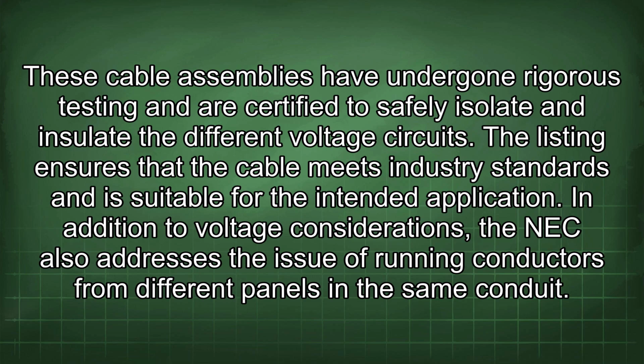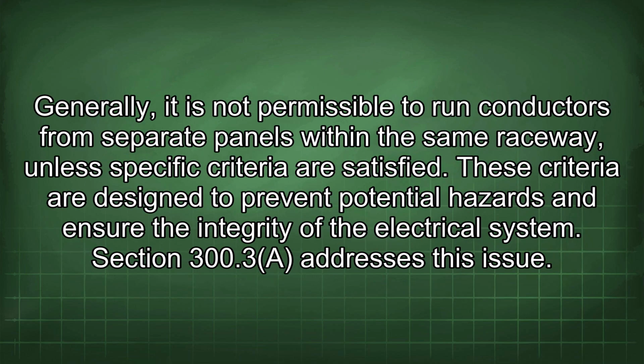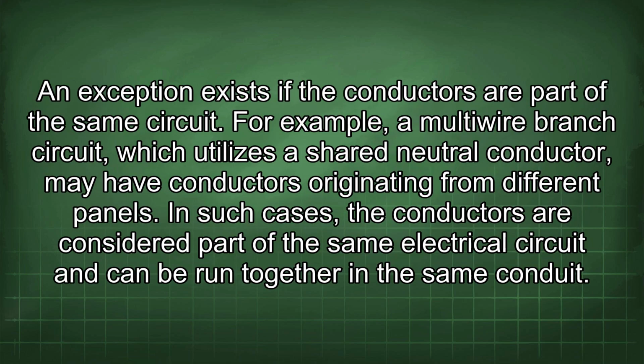In addition to voltage considerations, the NEC also addresses the issue of running conductors from different panels in the same conduit. Generally, it is not permissible to run conductors from separate panels within the same raceway unless specific criteria are satisfied. These criteria are designed to prevent potential hazards and ensure the integrity of the electrical system. Section 300.3 addresses this issue. An exception exists if the conductors are part of the same circuit.